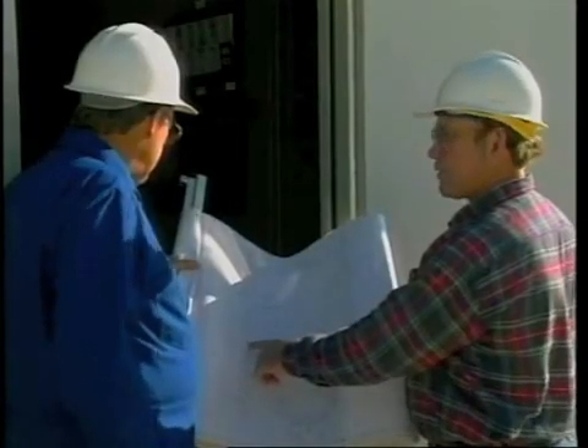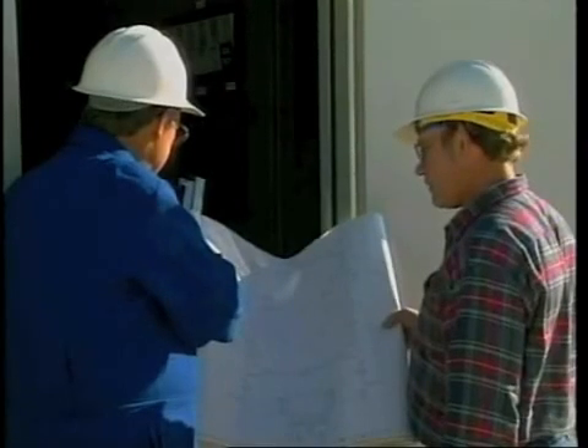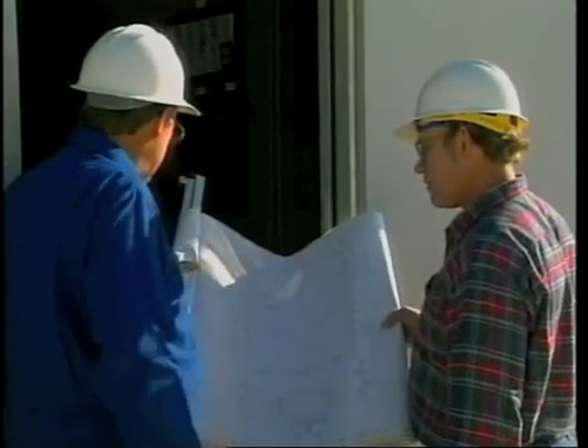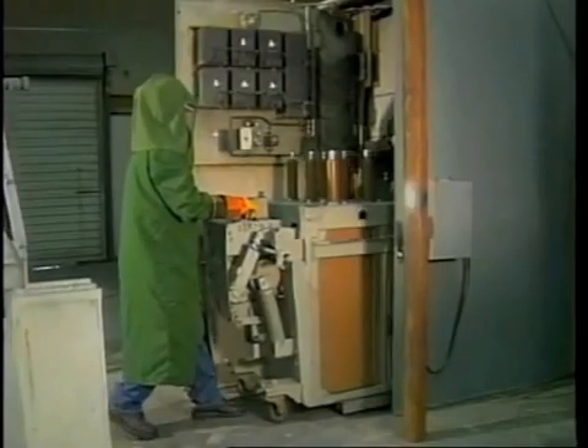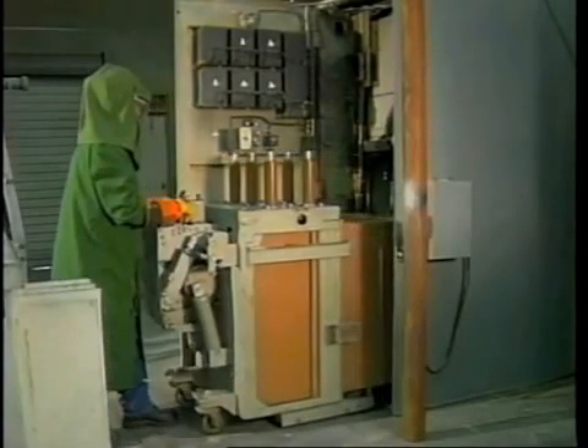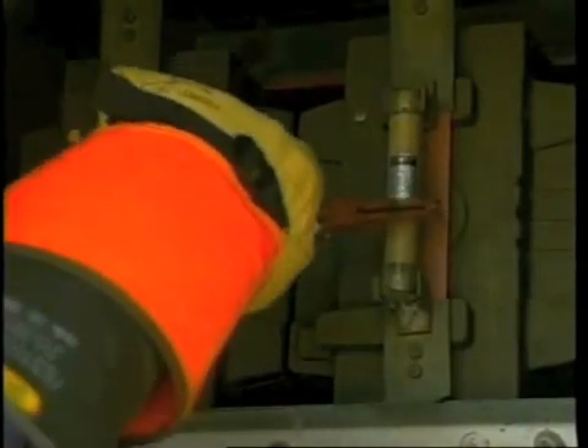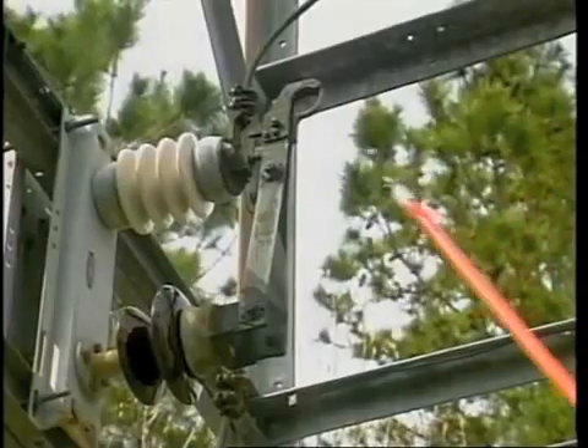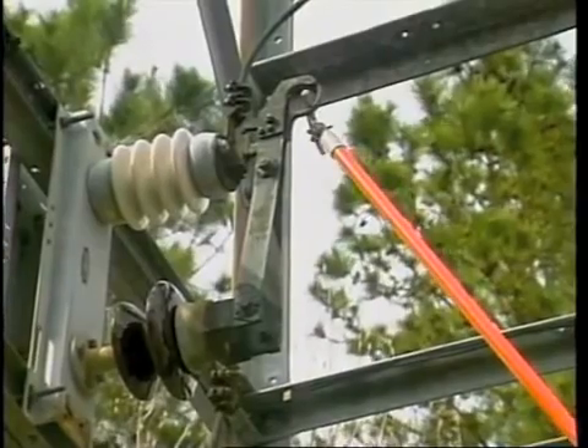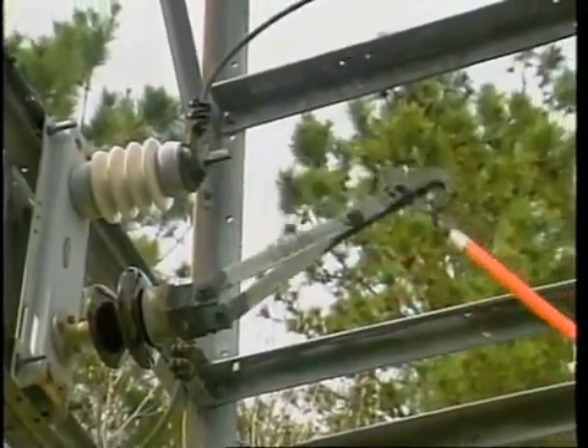First, review operating one-line diagrams and identify all power sources that are part of the system you're working on. Second, open circuit breakers and rack out if necessary. Open switches. Remove potential transformer fuses, and take any other action needed to put a visible air gap between all power sources of the system you're going to work on.